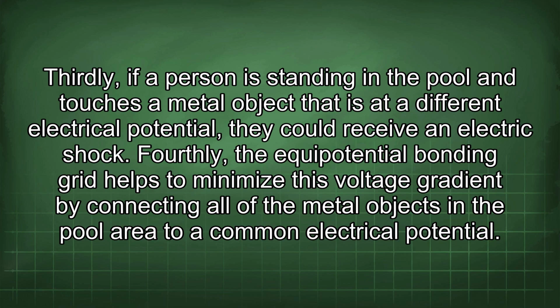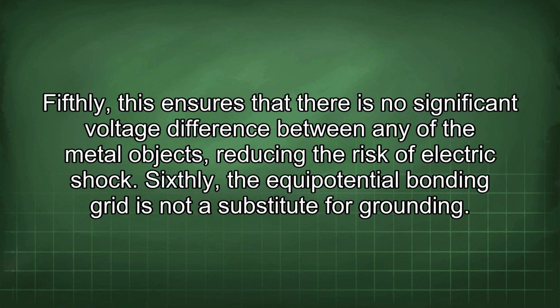Fourthly, the equipotential bonding grid helps to minimize this voltage gradient by connecting all of the metal objects in the pool area to a common electrical potential. Fifthly, this ensures that there is no significant voltage difference between any of the metal objects, reducing the risk of electric shock. Sixthly, the equipotential bonding grid is not a substitute for grounding.